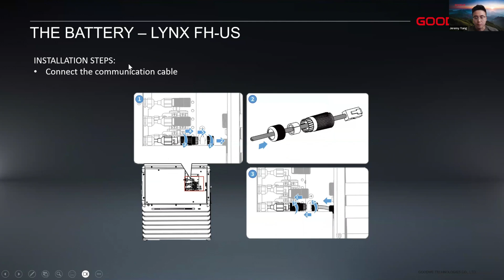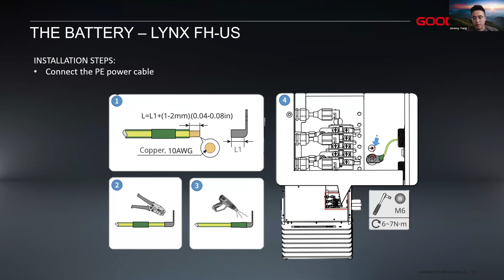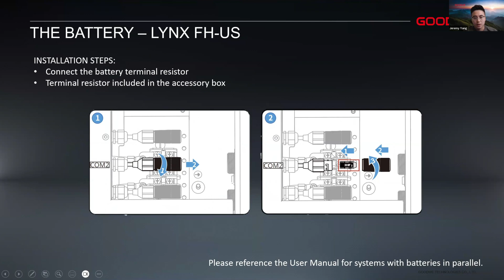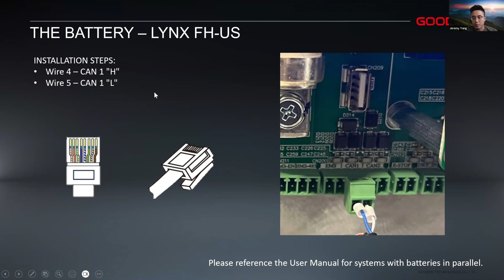First, the communication cable: open this, plug in the RJ45, and connect to the ground. For the DC side, use 8 AWG. Open the second terminal and plug in the terminal resistor. Wire 4 goes to CAN 1 high, and wire 5 goes to CAN 1 low, then plug it in.